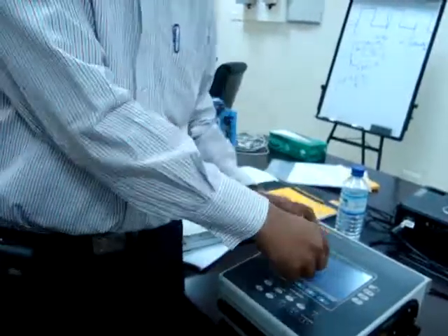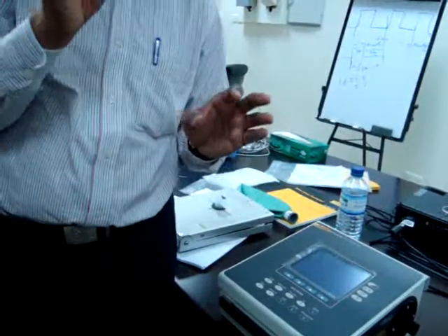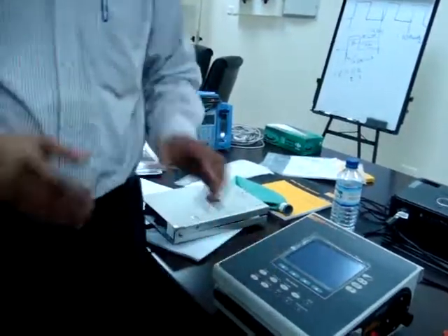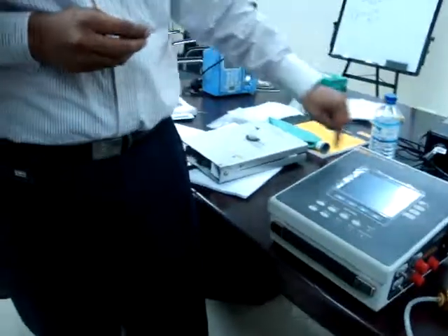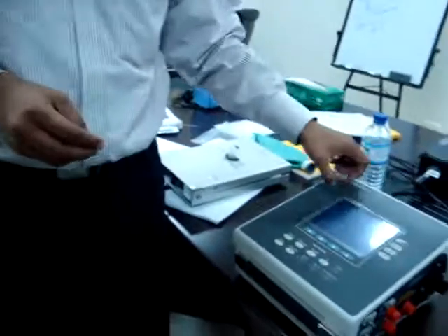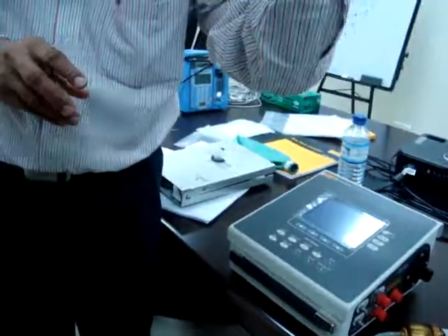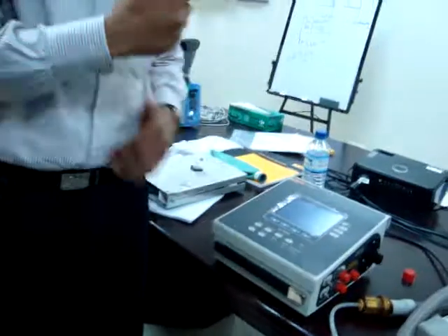Once I switch on the machine, I will show you the combination. You can select and show. At any point of time, the screen will show 4 parameters. Flow, pressure, with the gas passing through the tube. There is a tubular structure where the transducers are located, which will take the flow, and also it will calculate the volume. It will calculate the pressure. With that, it will make all kinds of arrangements.